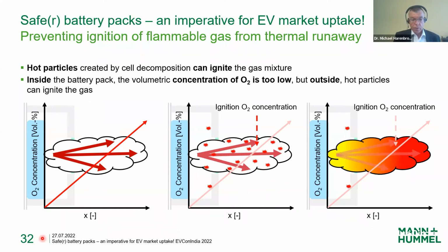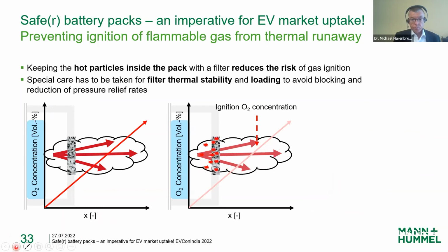And so this is, of course, something you would like to prevent. And so one solution to do this is to add a filter function here, which keeps those hot, and in this case larger, particles from being ejected from the battery pack. So you more or less take one of the three elements which you need for a fire - the flammable gas, the oxygen, and the heat source - out of the equation. And so this helps you to reduce the risk of battery fires.